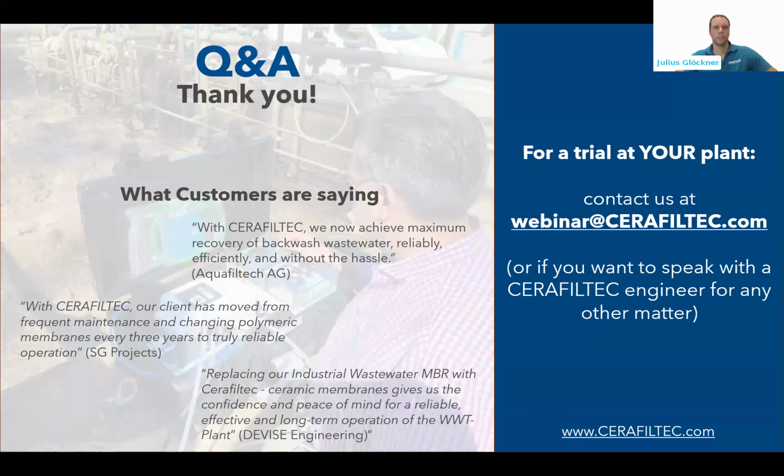Excellent. And then the last question here in the chat: how does the pre-treatment quality compare to PES UFs with a smaller pore size for RO pre-treatment applications? Also a very good question, actually. What we have experienced so far is that, due to the fact that we have no fiber breakages, the filtrate quality is always in shape, meaning turbidity is in the same range as from a polymeric membrane, which has smaller pore sizes.